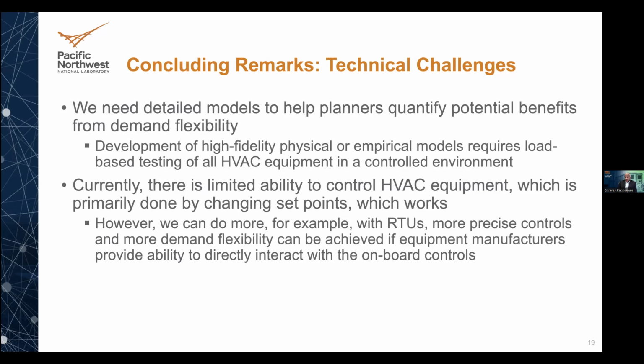Second, currently there is limited ability to control HVAC equipment, which is primarily done through changing set points, which works. However, we can do better. For example, with RTUs, more precise control and more demand flexibility can be achieved if equipment manufacturers provide the ability to directly interact with the onboard controls.